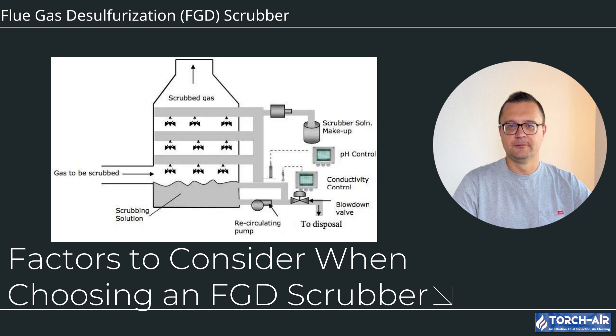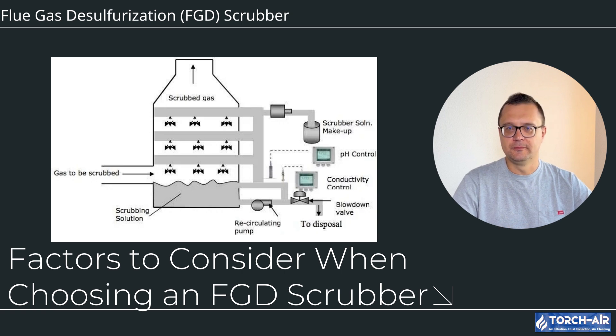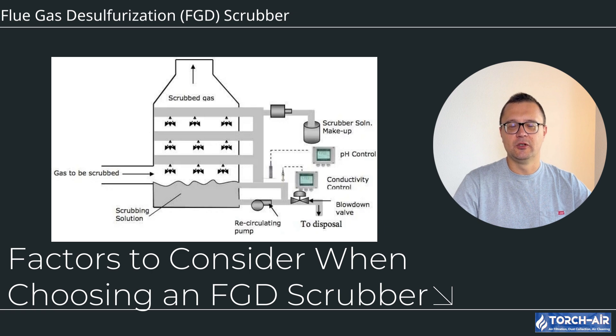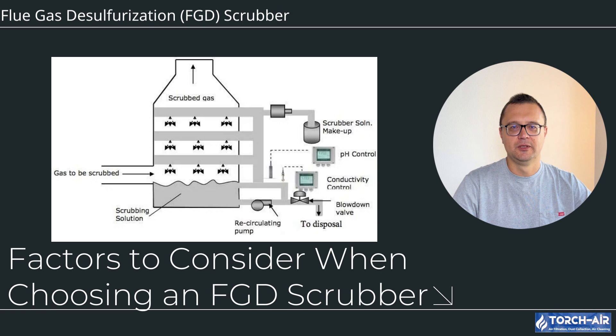Factors to consider when choosing an FGD scrubber: First, measure the total flue gas volume produced to ensure the system can handle the load — capacities are usually measured in cubic feet per minute (CFM). Second, determine the SO2 concentration in the flue gas, as higher concentrations will require more robust scrubbing systems. Third, consider water availability — if water is a limiting factor, dry scrubbers might be the best choice, however wet scrubbers are more efficient in terms of SO2 capture.